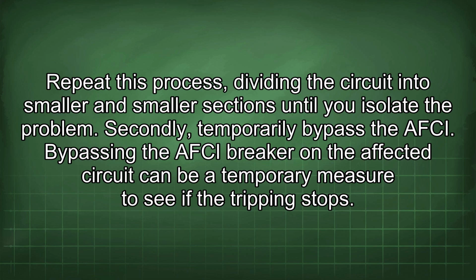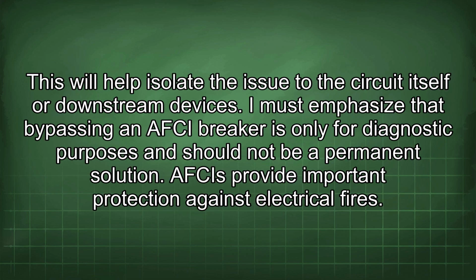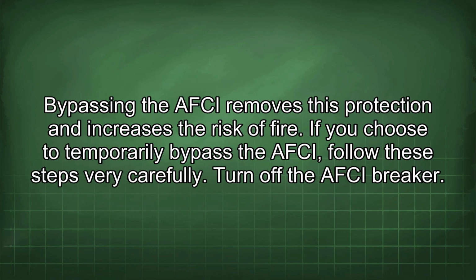Bypassing the AFCI breaker on the affected circuit can be a temporary measure to see if the tripping stops. This will help isolate the issue to the circuit itself or downstream devices. I must emphasize that bypassing an AFCI breaker is only for diagnostic purposes and should not be a permanent solution. AFCIs provide important protection against electrical fires. Bypassing the AFCI removes this protection and increases the risk of fire.